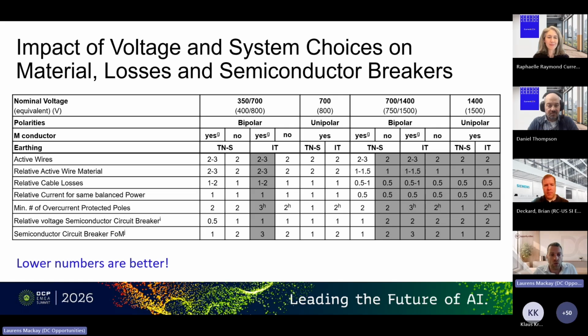And then what is important next, if you're thinking about solid state breakers that are very interesting for data centers and DC in general, it's important to think about, okay, what kind of voltage do they need to block? And there are some systems, especially the unipolar systems and systems with an M conductor, they can only block 1 pole voltage, whereas the other breakers, they need to block the pole-to-pole voltage. So that's the difference there.